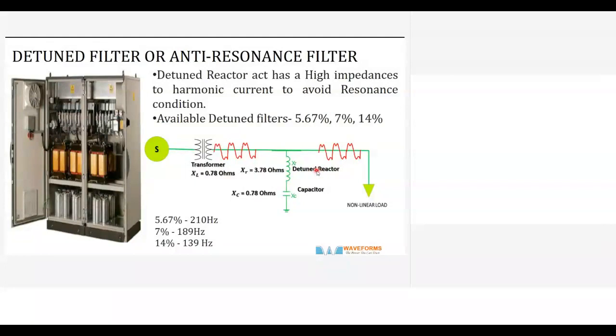Okay, so 14% means the two will be in resonance up to 139 hertz. Yes. It is away from 150 hertz, so at 139 hertz it does block the third harmonic. But resonance means the resistance will be low, right? At that time, will it block or will it pass? It will have a high reactance to the third harmonic. Okay, it is blocking. When you say 14% impedance, it means the inductor is wound more. The windings are more, so the magnetic flux also increases in the inductor. So it becomes a high impedance path for that particular frequency generated in the network. So it's a blocking. That impedance will decrease, right?